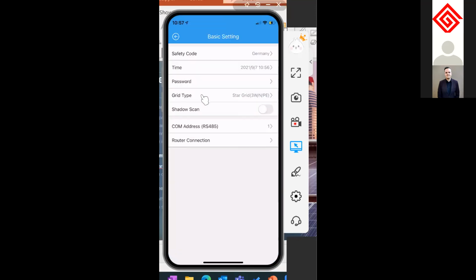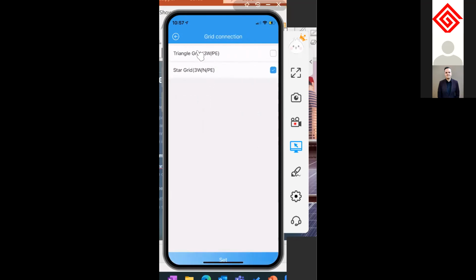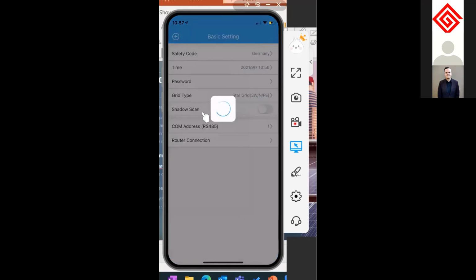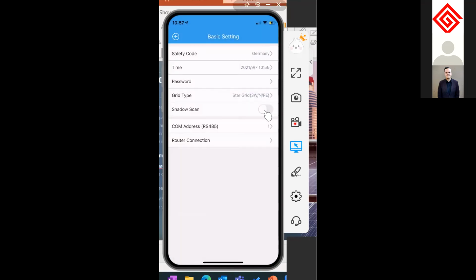Then going back here, you select your grid type. So you have either a star grid or triangle grid, which is also called delta grid. Select the correct one. In this case, it's already selected. Then we go to the next type. And we will have to either choose to activate shadow scan or not. In our case, we have no PV module, so that's not a problem for us. So I will leave that off.